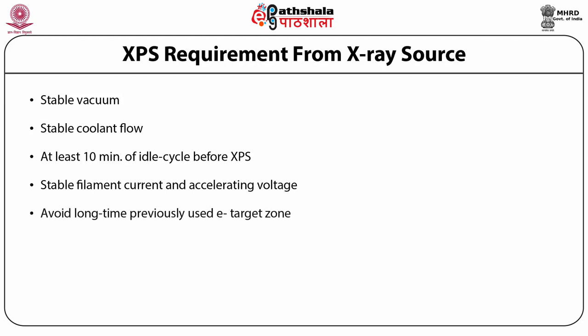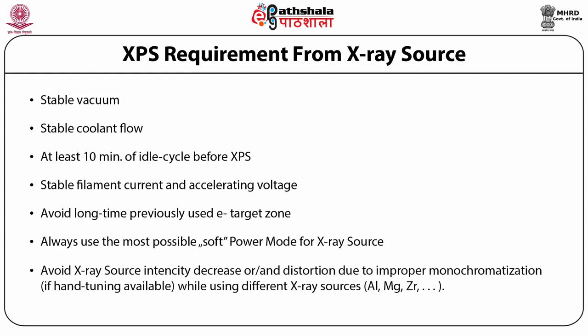XPS requirements from the X-ray source: it should have a stable vacuum and a stable coolant flow. At least 10 minutes of idle cycle before the XPS experiment is needed. A stable filament current and accelerating voltage are required. Avoid long time use of a previously used electron target zone. Always use the most possible soft power mode for the X-ray source. Avoid X-ray source intensity decrease or distortion due to improper monochromatization — in case hand tuning is available. Different X-ray sources include aluminium, magnesium, zirconium, etc.